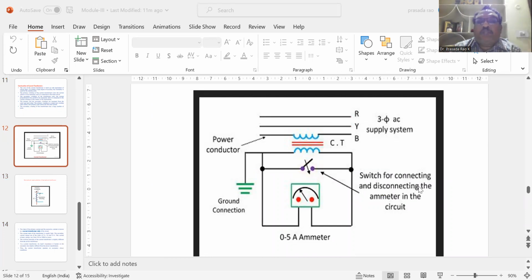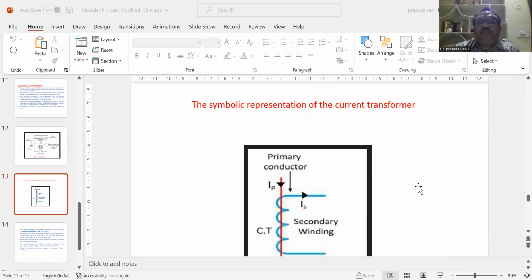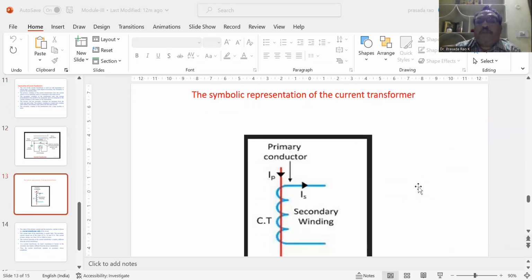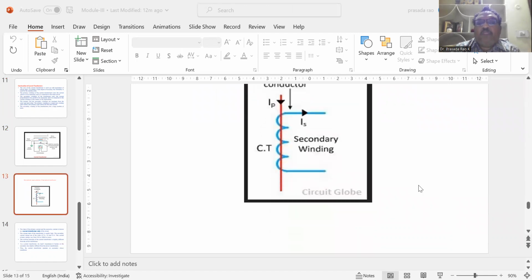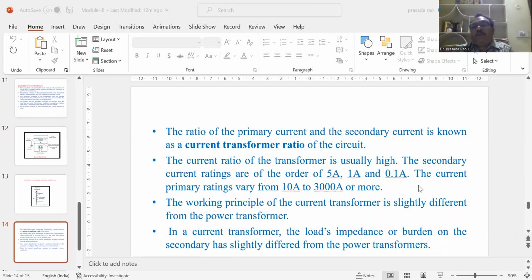Here the primary winding with a very small number of turns is connected, and the current to be measured flows through it, and the ammeter is connected in series to the secondary winding. This is the symbolic representation of a current transformer. The ratio of the primary current and the secondary current is known as the current transformation ratio of the circuit. The current ratio of a transformer is usually high.